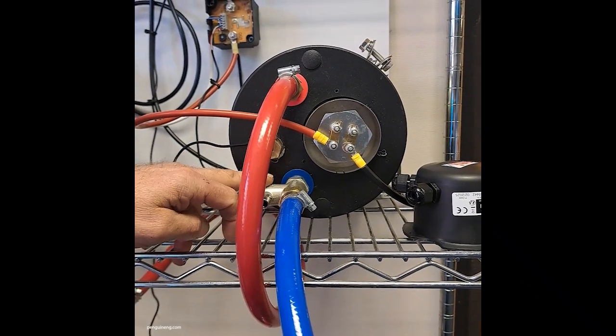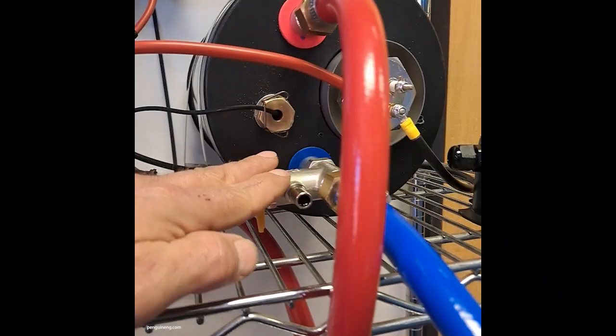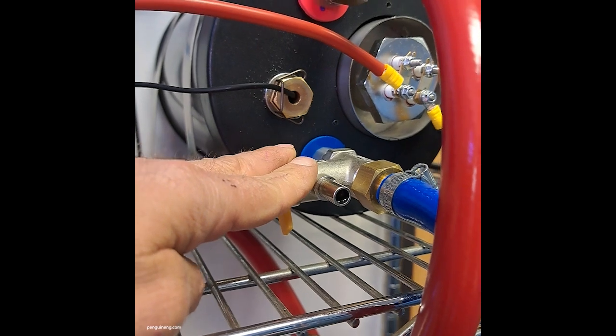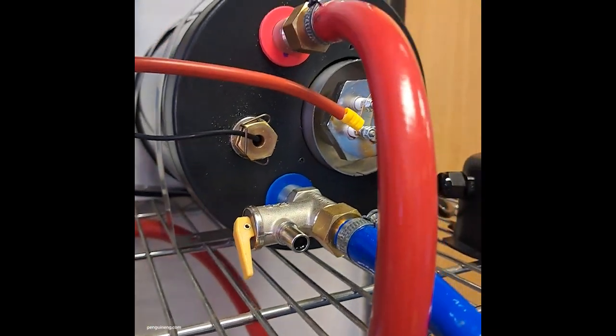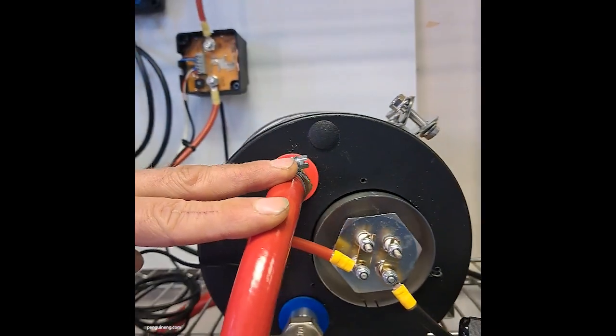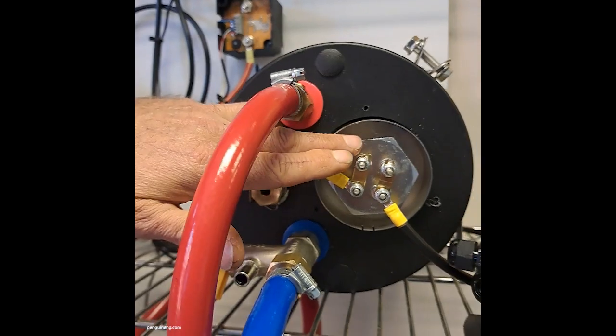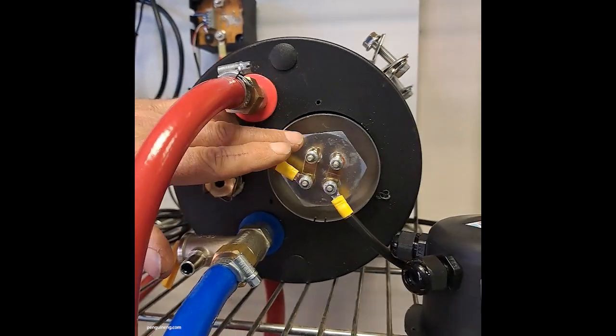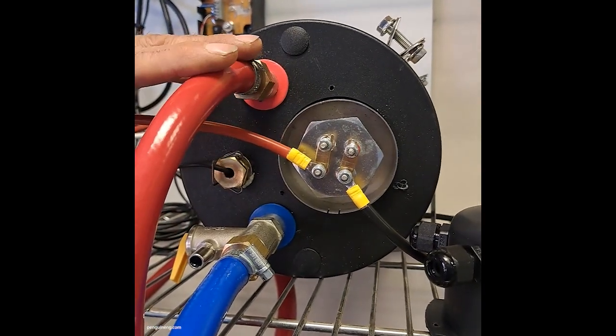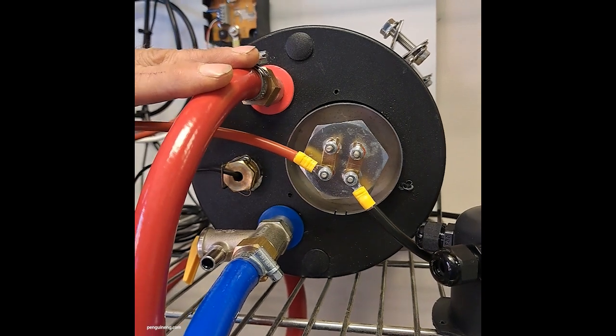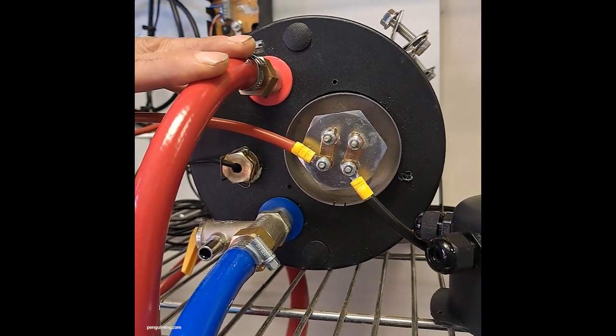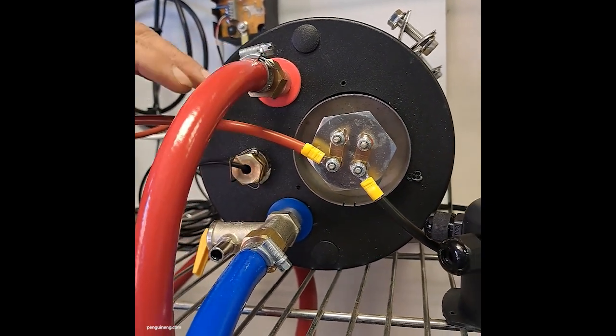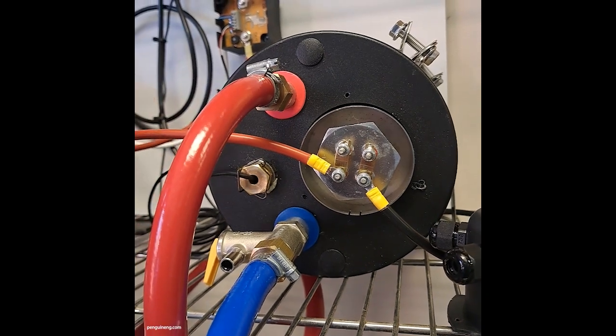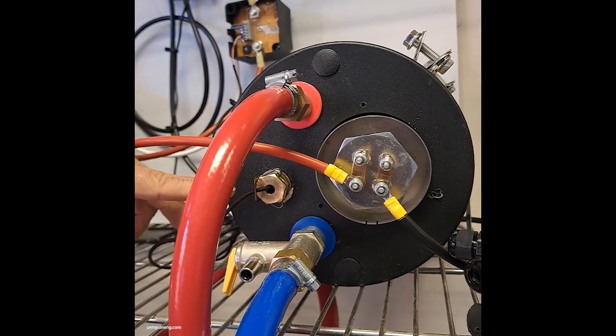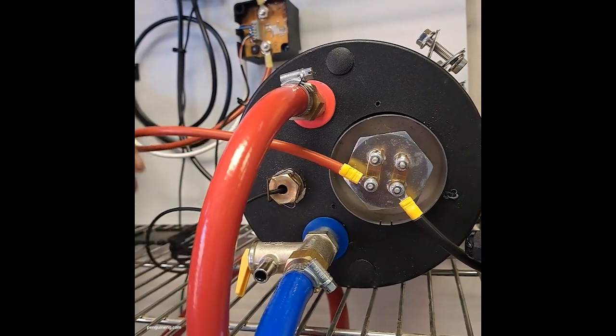On the opposite side, the blue pipe is connected to the cold water feed on the mini boiler. It enters through this pressure relief valve, which will protect the tank should the system become overpressurized for any reason. The hot water exits here. Just below it here is the heating element. It's important to install a hot outlet at the top. This will make sure the element is always covered with water and will allow any air to escape. The probe for the temperature sensor is located here and is connected to the controller.